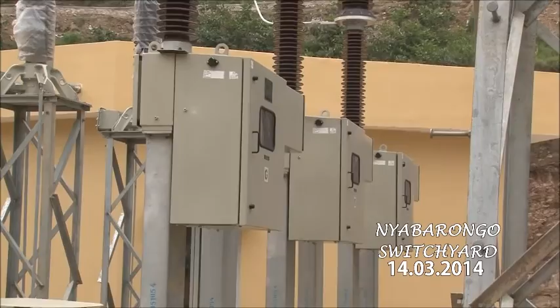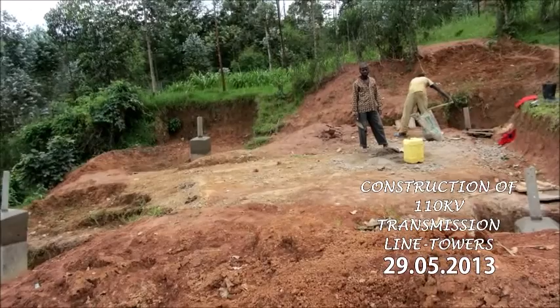Between the switchyard and Kilinda substation, there is a 110 kV transmission line. The total length of the transmission line is 27.5 kilometers and is erected on 78 towers. Installation of towers and stringing of conductors has been completed. Installation of 30 kV towers is under progress.